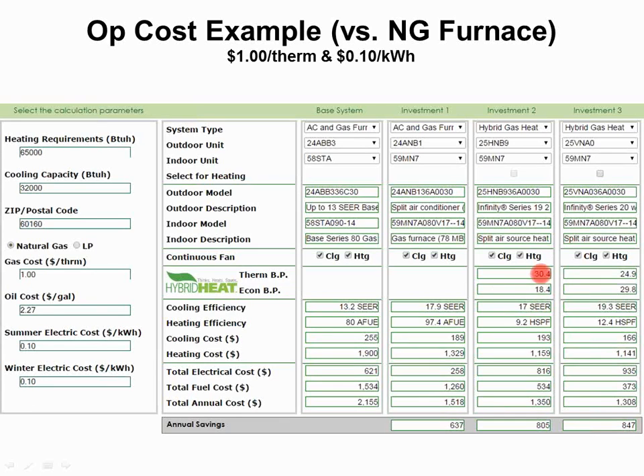Right now, what I have to do in this case is set my system up to change over at 30 degrees because I got to be able to cover the BTUs. So whenever it's below 30, boom, I go to gas furnace. Above 30, boom, heat pump. The last column is a variable speed heat pump with that same exact 97% furnace. You can see in this case, his thermal break point's a little bit lower. It's 25 instead of 30.